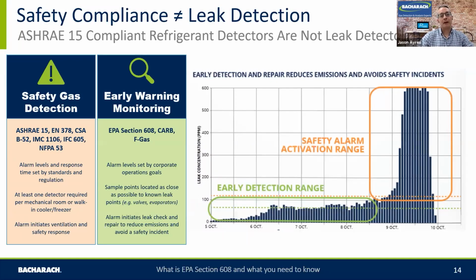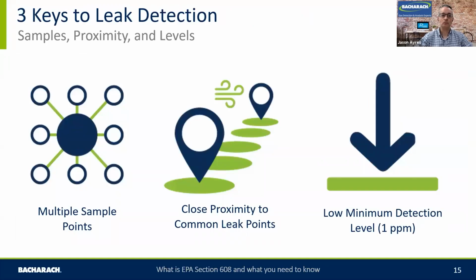So as well as safety compliance and moving to better deployment and leak detection, how else can you improve your leak detection within your facility? Improve the number of sample points. If you're looking at purely safety leak detection, you might have one sensor just on the wall in a large chiller room that will detect a high refrigerant emission, which is great for safety protection, but it doesn't help you reduce your overall refrigerant loss. First area is to increase the number of potential sample locations, or where you can pick up refrigerant leaks. The more sample points you have, the more opportunities you have to detect refrigerant leaks earlier.